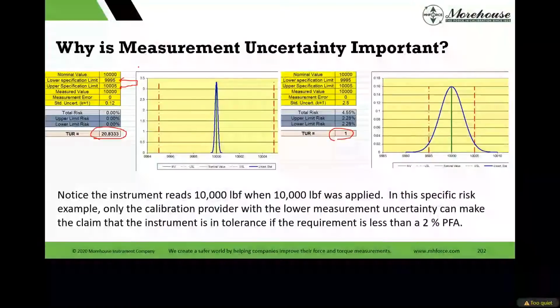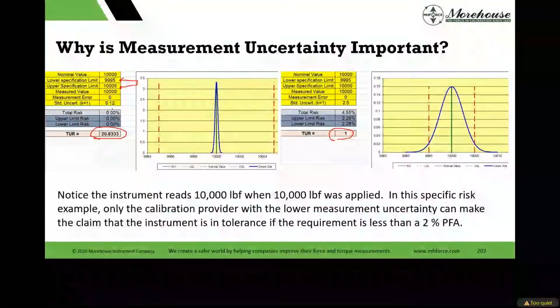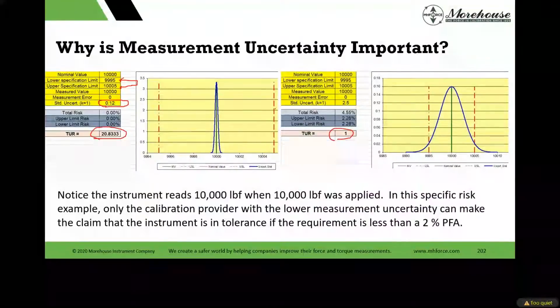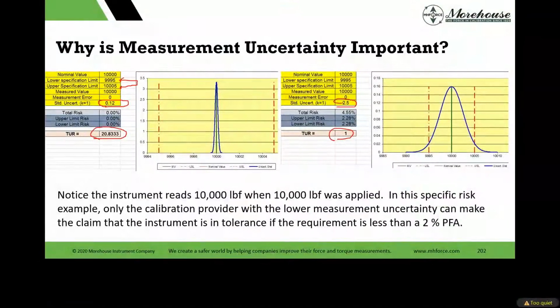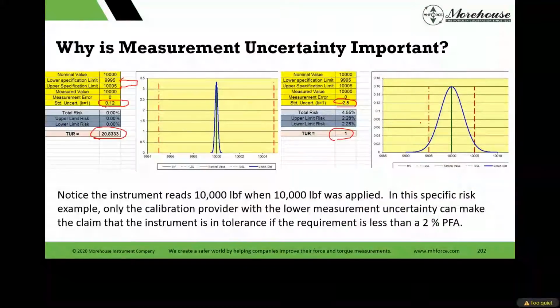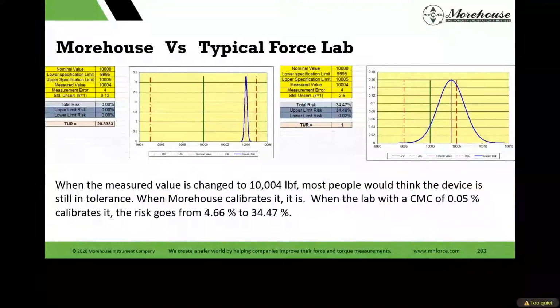Looking at these uncertainties and the risk, assuming the instrument has good resolution compared to the other machine, the TUR comes out to 20.83. What this shows is that the lower I can get the uncertainty, and the more correctly I can handle adapters and everything else, the more room I have to pass instruments.